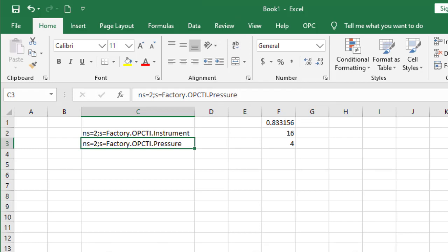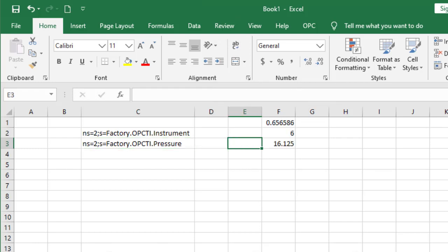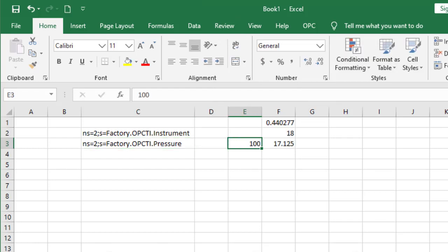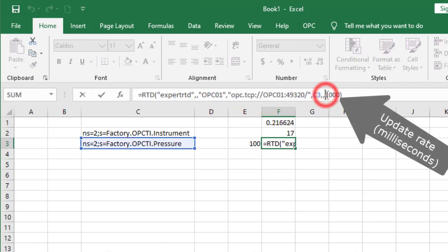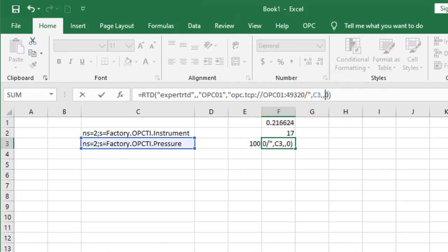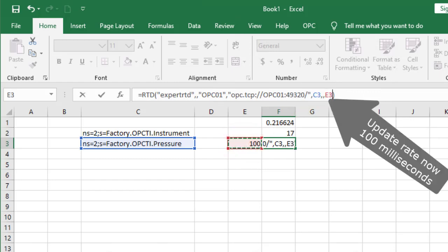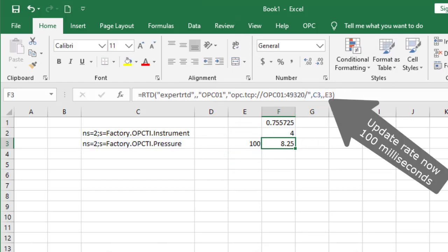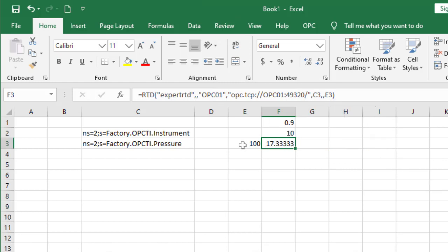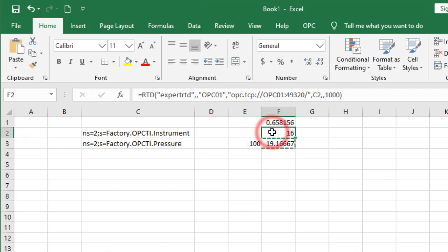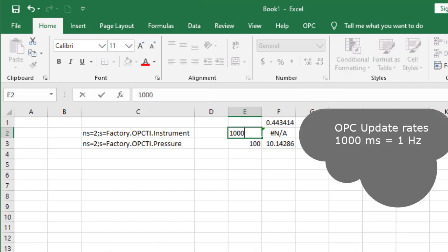Let's add another parameter. Edit the cell, and instead of 1000, we will refer to cell E3. This tells Excel's RTD to accept OPC data as fast as every 100 milliseconds, or up to 10 times per second from the OPC server. Let's copy F3 to F2. We see an error because F2 is pointing to E2, which is empty. When we say 1000, Excel begins updating at 1000 milliseconds, or once per second.